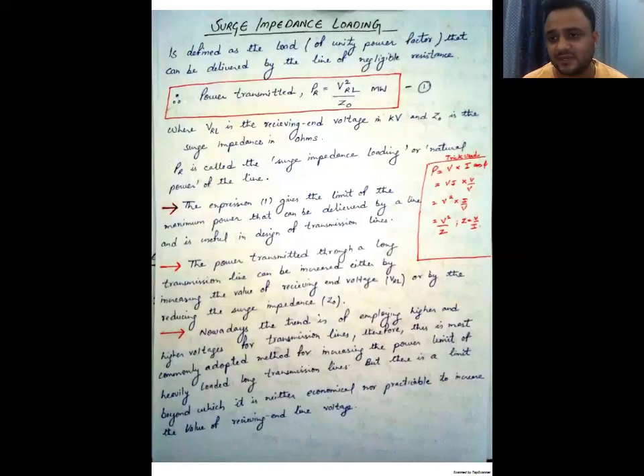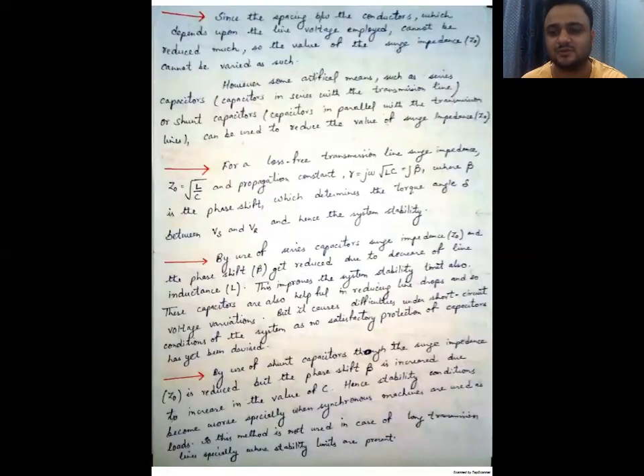Next, if we reduce the spacing between the transmission lines - but the spacing depends on the value of the line voltage, so that factor cannot be reduced to much extent. So that factor doesn't play a major role in reducing the surge impedance. Since the spacing between the conductors, which depends upon the line voltage, cannot be reduced much, the value of surge impedance cannot be varied as much.